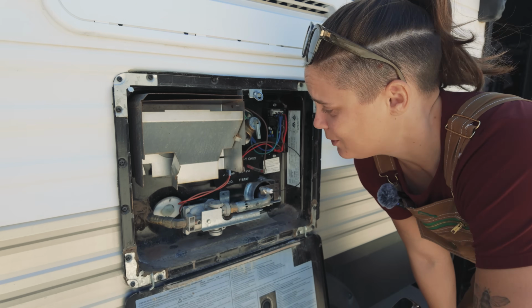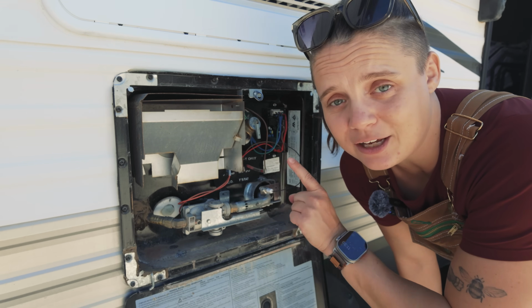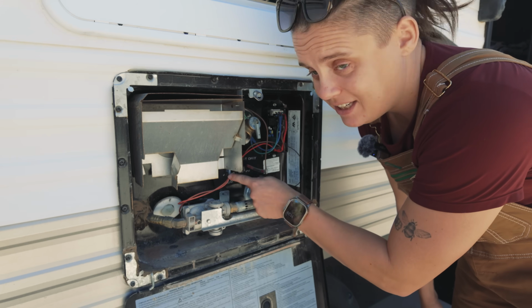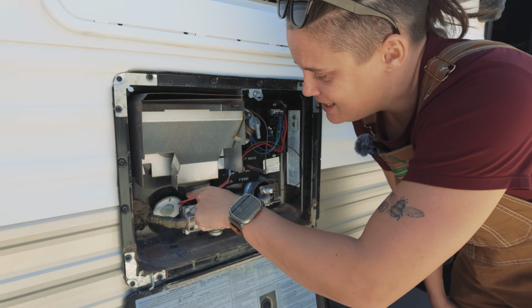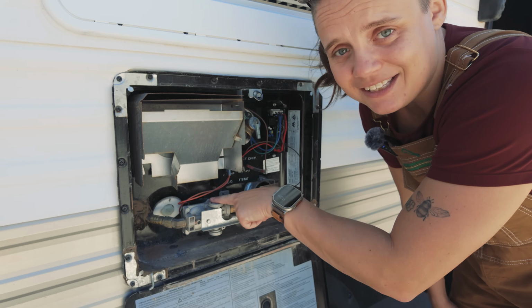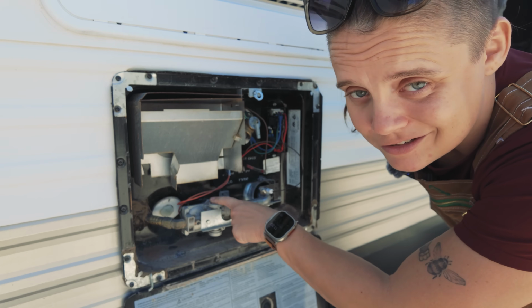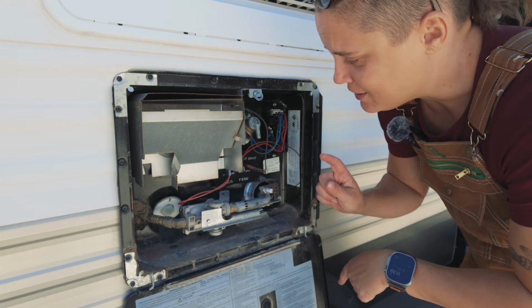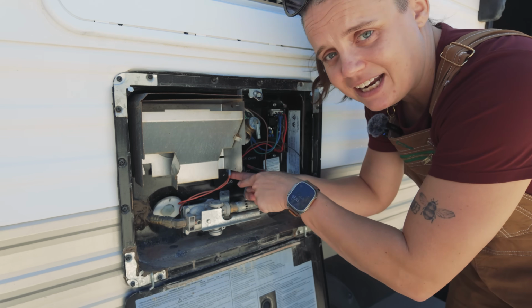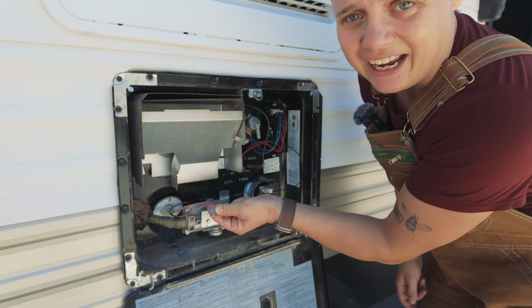The way you can test that solenoid is to head over to the last place we tested for electricity. You should see wires heading from there down to the gas valves—basically the only other thing with wires we haven't tested yet. Very carefully disconnect that terminal, so it's just hanging out right here.